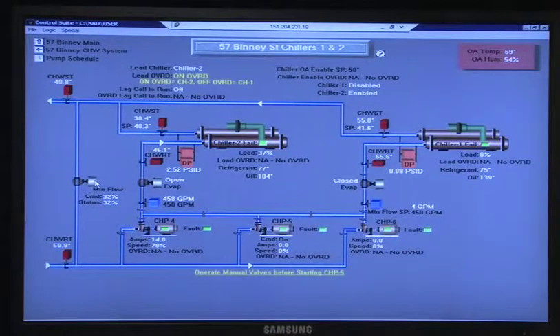So regardless, if the lead chiller comes on, when the plant's enabled for the first time, that happens. If the lead chiller is running and you start a lag, that goes on too. And the pump associated with the chiller that's called to run goes to 80-something percent for like 5 to 10 minutes, just to push enough flow to make all the flow switches, and then it releases it. There were some dynamics in the system they needed to overcome.